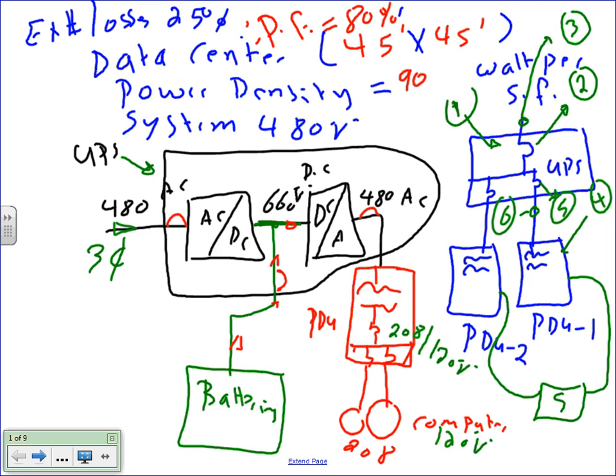Okay, so what do I need to do? You guys are familiar with the 480. The UPS system takes a 480 system, converts it into DC, typically 660 volt DC, ties it to the batteries, comes out of the batteries with AC, inverts it at 480, and dumps it at a PDU. The PDU has a transformer inside it. From the transformer, there's also a panel with a transformer in the same box. And from there, you can feed all your electronic equipment. These are all electronic equipment.